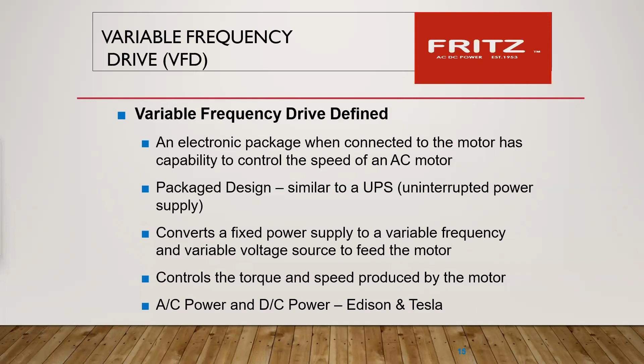A lot of factories today are looking at ways of saving, which I understand, but their big focus is keeping those machines running, and even doing these evaluations about noise and harmonics, which do happen from variable frequency drives because we're not a fixed sine wave coming out of the power source to them. We've got a lot of applications that are outside of that, and now with solar and wind, a lot of power quality concerns out there, and then voltage balances and information. So we really recommend getting the proper testing evaluations done on facilities.